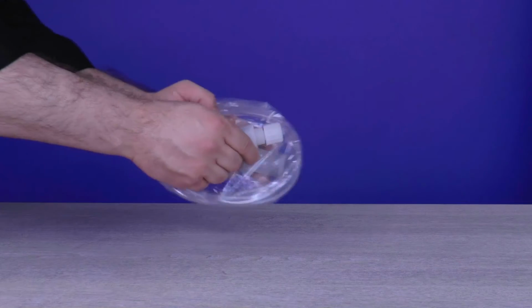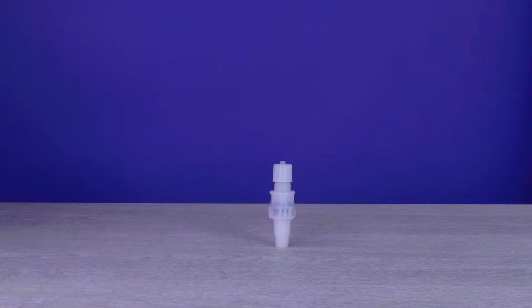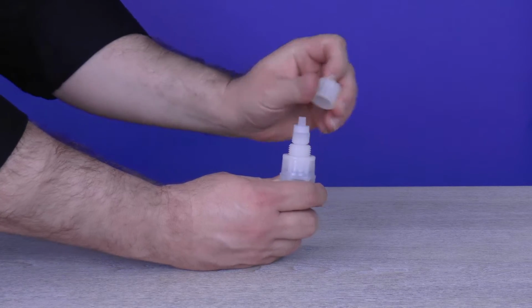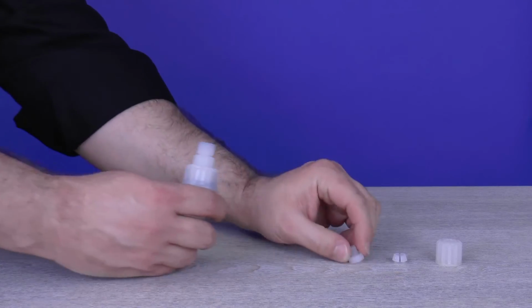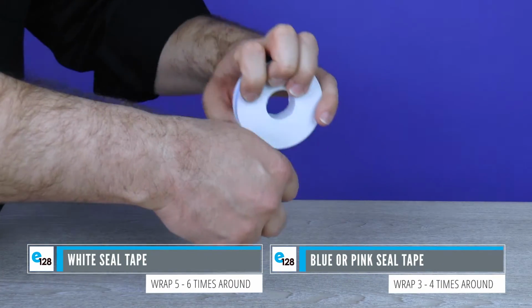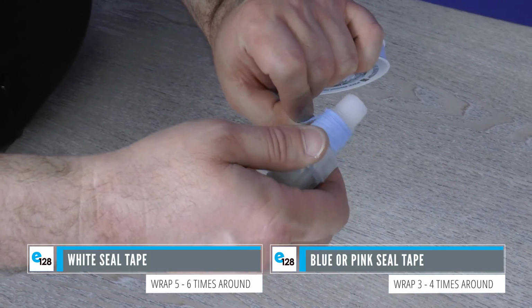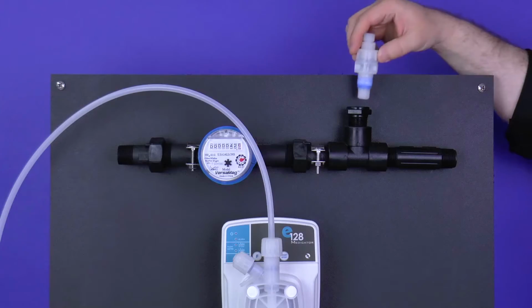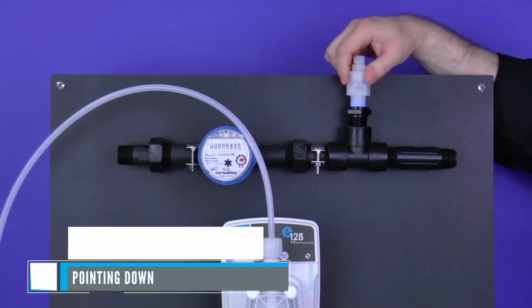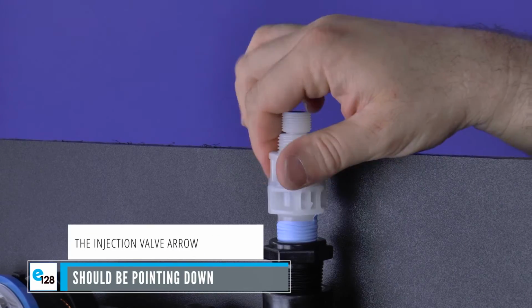Injection valve. Grab the injection valve out of the installation kit and remove the tube nut, collar, and nozzle. Set these items aside and make sure not to lose them. Take the thread seal tape and wrap it around the threads of the injection valve for the necessary size, either 3/8 or 1/2 inch. Install and hand tighten the injection valve into the installation saddle or T in the supply line. Once again, do not over-tighten.